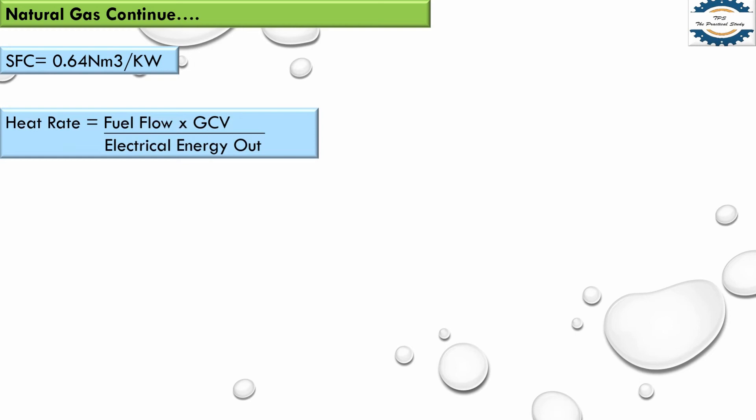Now we will calculate the heat rate, whose formula is fuel flow multiplied by GCV divided by electrical energy output. GCV is the gross calorific value — it is a constant for each fuel and depends on fuel quality. The greater the quality of fuel, the higher the GCV value. You can find your GCV value from your fuel supplier.